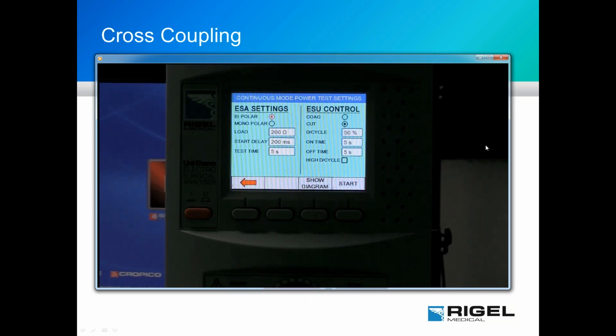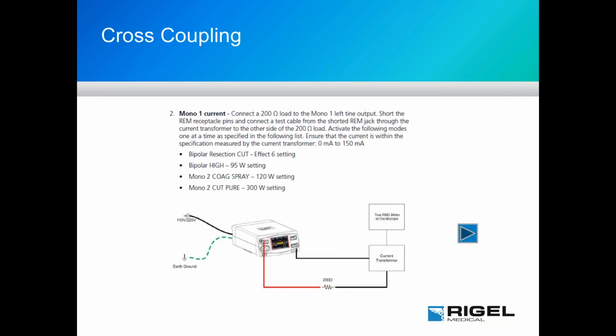One thing I would like to share with you here is you saw that our display showed less than 1 watt, and that is an acceptable reading because what it's really saying is the steering circuitry inside the generator itself is working per design. You could see a little bit of current being output from time to time, but again, never more than 150 milliamps. So a common question we always receive is, hey, I'm doing this test and I'm getting less than 10 milliamps, I'm getting less than 1 watt. Am I doing something wrong? And the answer is no, that is a typical reading when you're doing a test on the FT10.